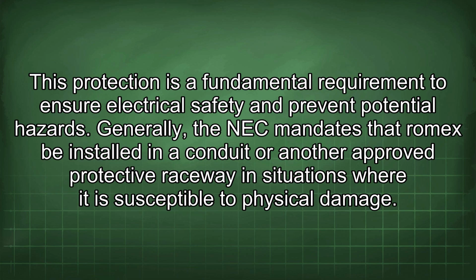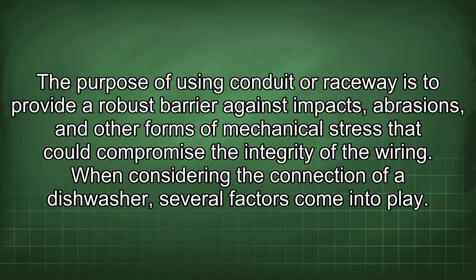Generally, the NEC mandates that Romex be installed in a conduit or another approved protective raceway in situations where it is susceptible to physical damage. The purpose of using conduit or raceways is to provide a robust barrier against impacts, abrasions, and other forms of mechanical stress that could compromise the integrity of the wiring.